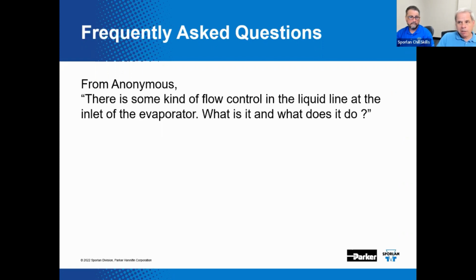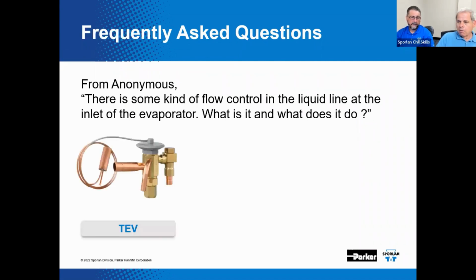Well, here's another really good question from Anonymous. It says, there's some kind of flow control in the liquid line at the inlet of the evaporator. I'm not sure what it is. I'm not sure what it does. John, can you tell us about that? That's an excellent question. It could be basically one of three things. It could be a thermostatic expansion valve or a TEV. Yes. What would that do? It would be used to control superheat at the location of the sensing bulb. The copper cap tube connects the bulb to the diaphragm housing or thermostatic element on top of the valve body. And then over here to the sensing bulb.